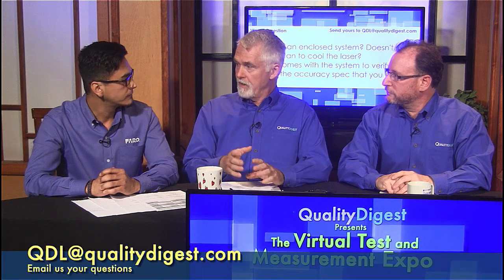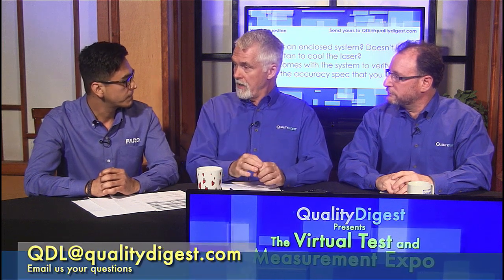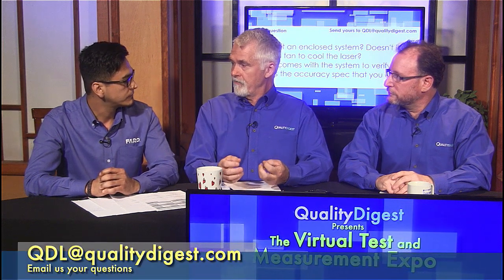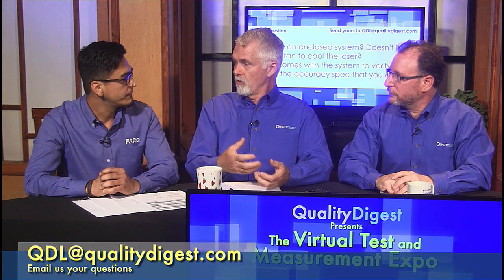Wonderful. And I believe, just to repeat one of the unique things about the calibration, in case they didn't catch it, is that I believe you said you calibrate once, and the calibration information for that probe tip is now stored within the system itself. Correct. And it recognizes the probe. Right. With the new Quantum, you only need to calibrate your probe once. It comes with a 6mm and a 3mm. And you calibrate those the first time you're going to use them, and then you can swap those and you won't need to calibrate. So that really helps speed up the inspection process without the need to go into the software and recalibrate your probe each time.